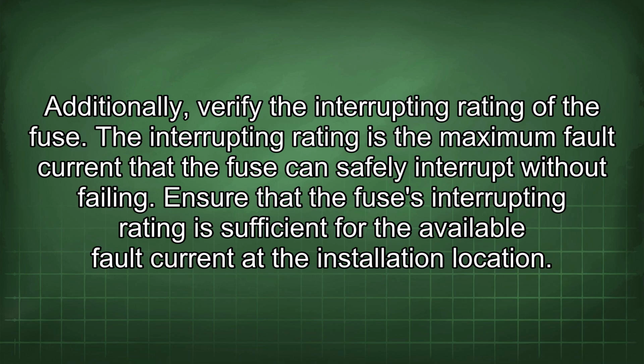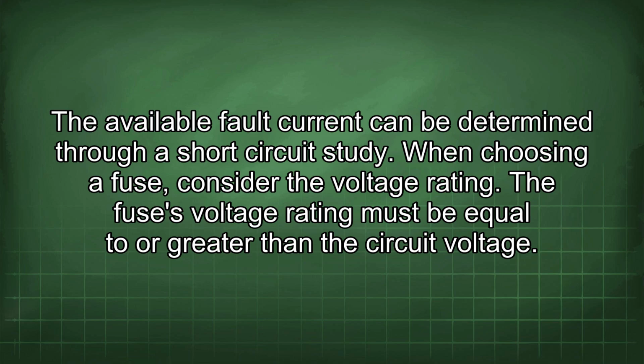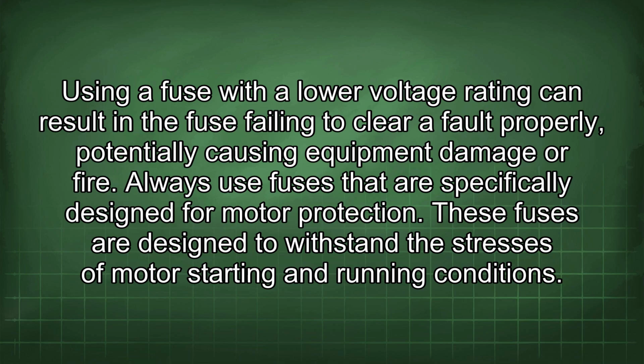Additionally, verify the interrupting rating of the fuse. The interrupting rating is the maximum fault current that the fuse can safely interrupt without failing. Ensure that the fuse's interrupting rating is sufficient for the available fault current at the installation location. The available fault current can be determined through a short circuit study. When choosing a fuse, consider the voltage rating. The fuse's voltage rating must be equal to or greater than the circuit voltage. Using a fuse with a lower voltage rating can result in the fuse failing to clear a fault properly, potentially causing equipment damage or fire.